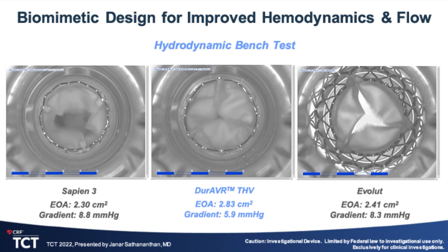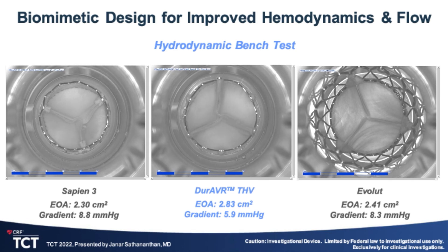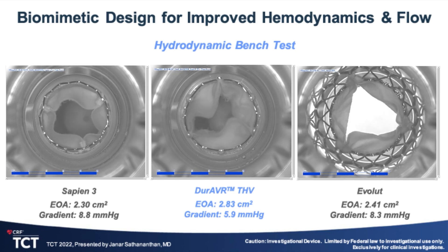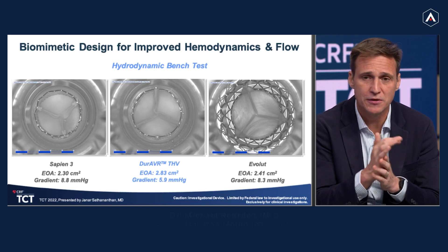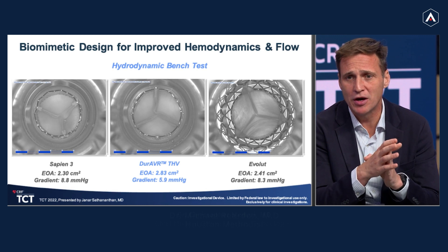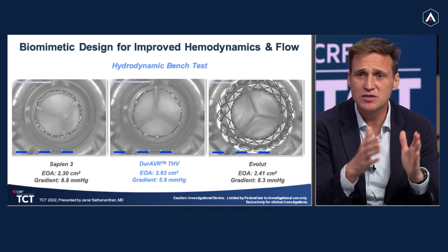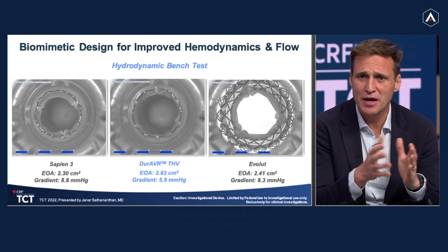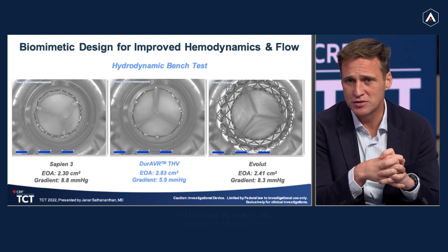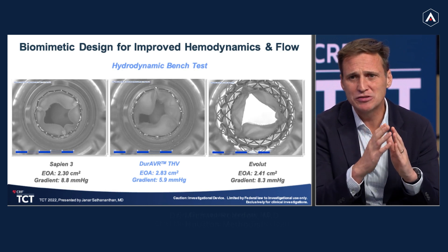When you see the images in front of you comparing this valve to other valve technologies on the hydrodynamic testing — this testing was done by Janarsanth and Nathan last year — what you can see is that when you compare this unique biomimetic valve design to competitor valves such as Evolut and Sapien, there is significantly better hemodynamic performance. Because of this unique design, there's a much larger opening area and a much more native-like opening of the valve.